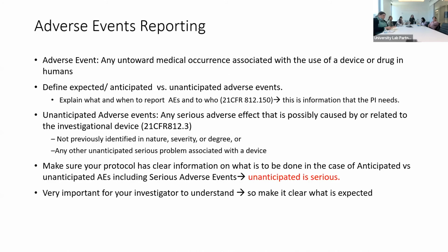Adverse event reporting. So this is important to think about in relationship to your device, right? Like, what does it do? If you have a sensor with a spring on it, right, could an adverse event be to indent the tip of the finger? Yeah. Because if you don't put it in there, then it's an unanticipated adverse event, which automatically gets reported.